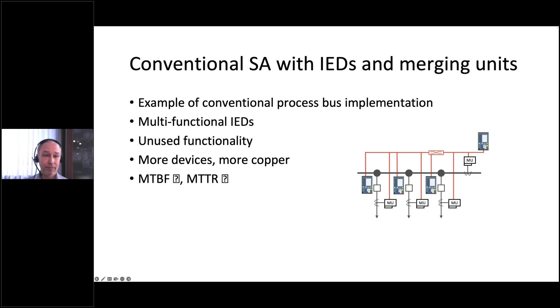When functionality is allocated in a more central point, like a substation server running applications in a dedicated virtual machine, less hardware is needed. This makes the physical design of secondary systems less complex. Some functionality still needs to be located close to the process, like TCTRs and TVTRs, and also switching capabilities for disconnectors and circuit breakers. These functions can be hosted by lower cost sensors and actuators. Because of the more simple design of these devices, the lifespan is longer and the configuration is simpler. This results in a longer mean time between failure and shorter time to repair.